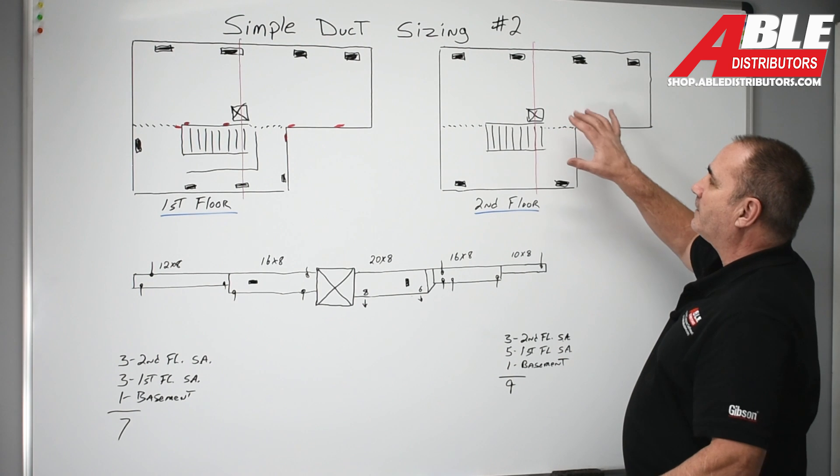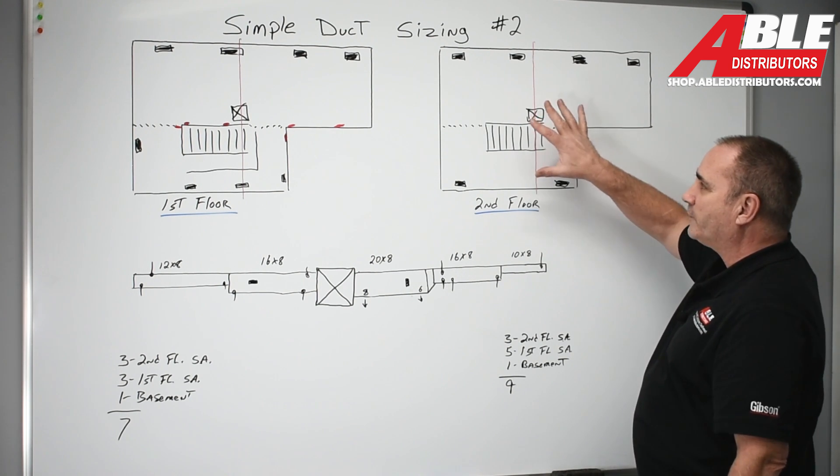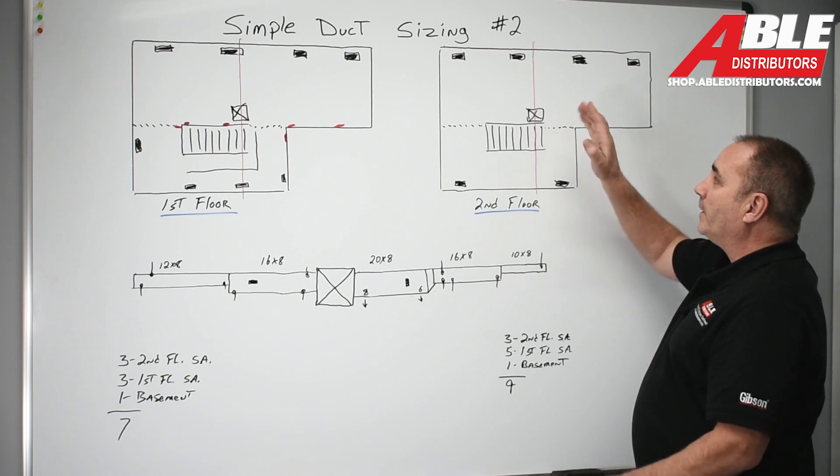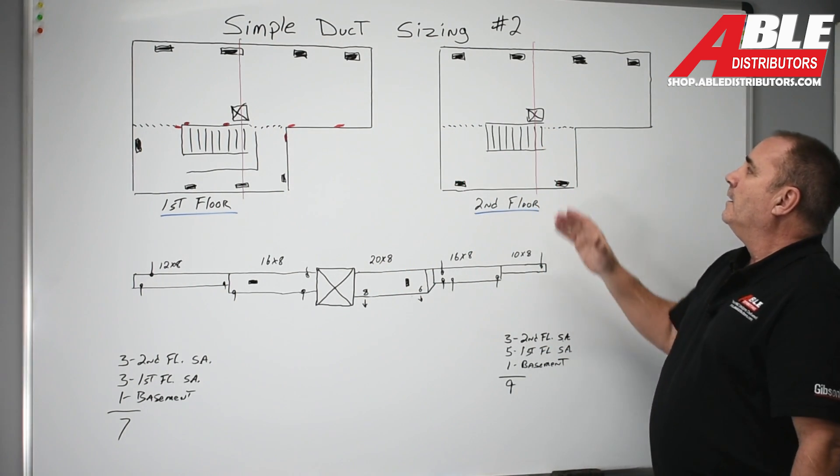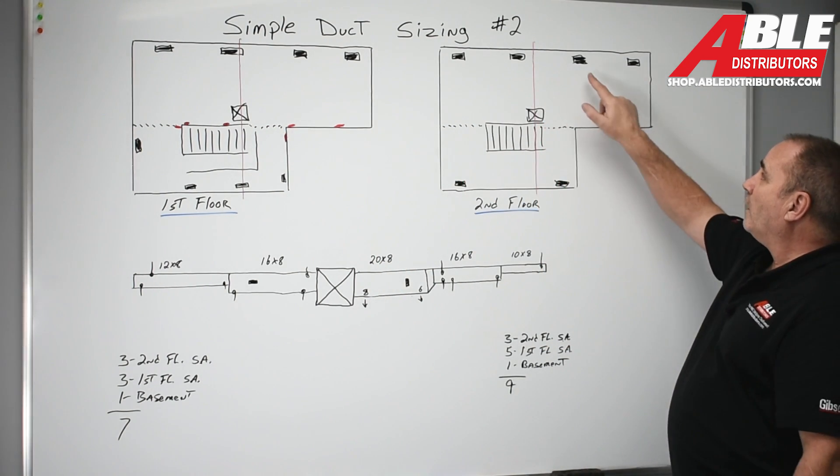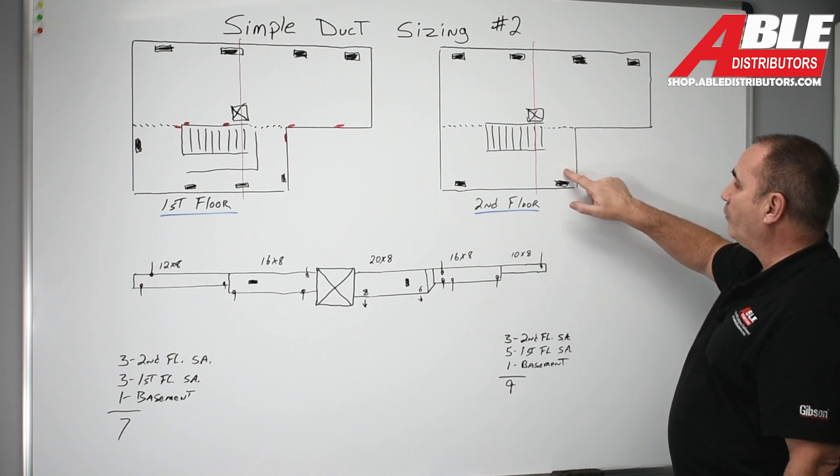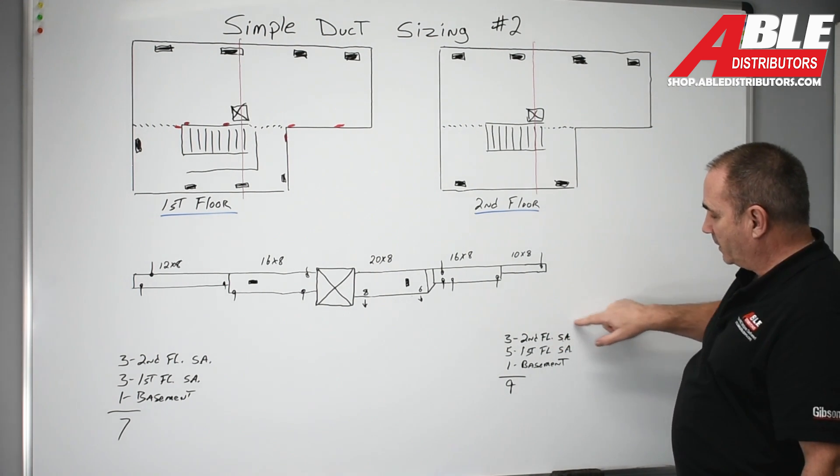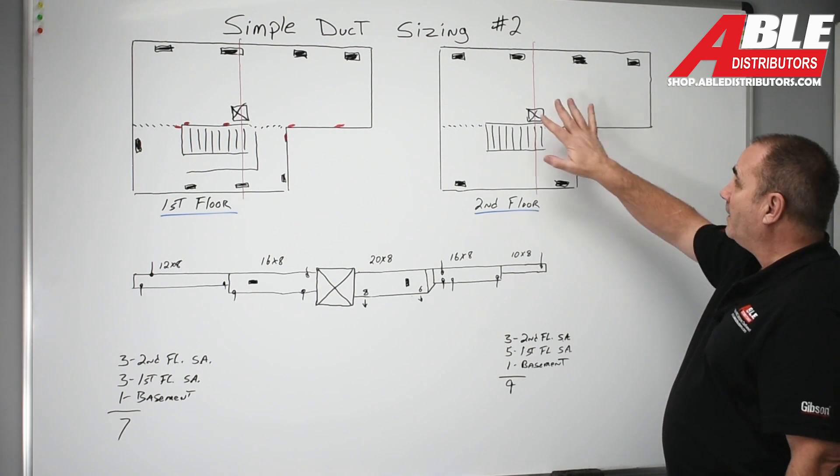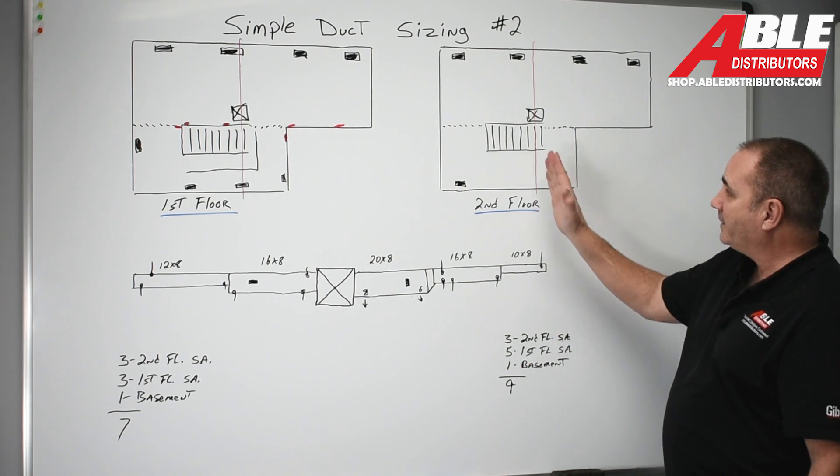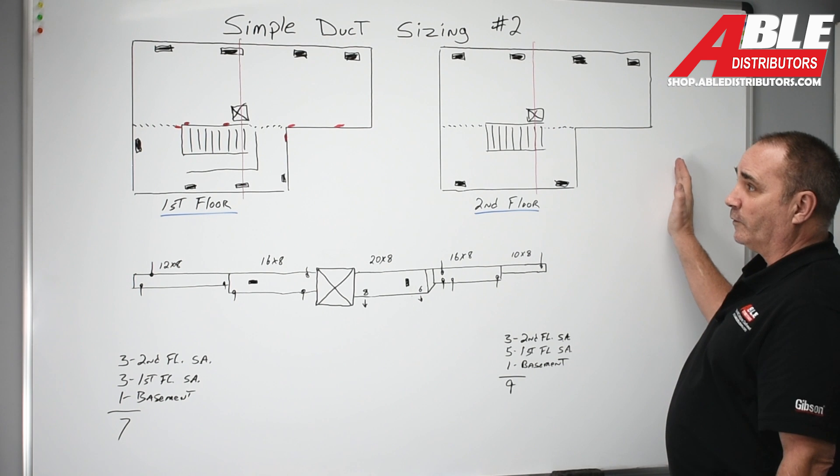Second floor I do the same exact thing. I draw the furnace. No, the furnace is not going to sit on the second floor but I know that's where it's going to sit in the basement just past the stairwell. So now I know on the second floor I've got one, two, three - three second floor supplies. I'm going to put one in the basement on this half of the basement. That gives me a total of nine supplies to the right of that furnace.